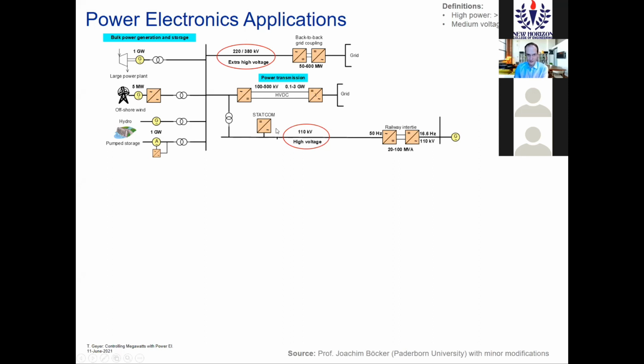Then we have static synchronous compensators. They're also power electronics. We have railway interties. We connect a 3-phase AC 50 hertz system to a single phase, maybe 16 2/3 hertz grid. And then we have offshore wind feeding into that system. So at the time, those were 5 megawatt wind turbines. Nowadays, we have 12 megawatt plus for offshore wind. The development is moving towards 16, 17 megawatt.